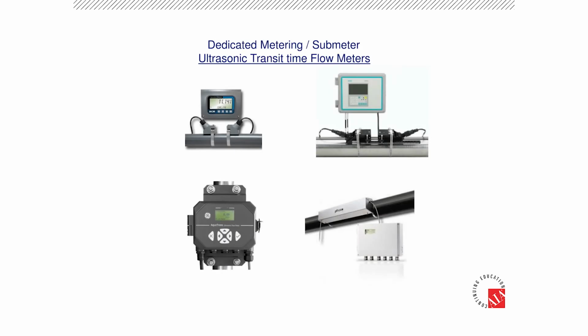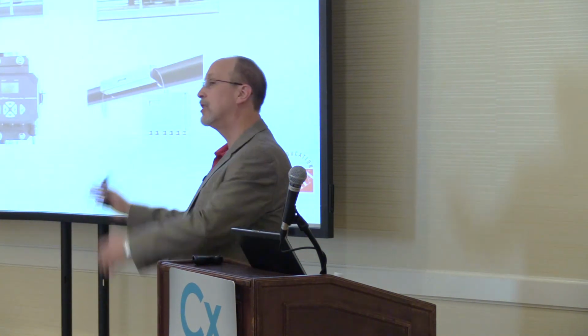Dedicated ultrasonic flow meters are primarily devices that were used in the sub-metering application. Why? Because the prices are getting so low. You can buy a dedicated transit time flow meter for about $2,000 now. The price of a paddle wheel flow meter is about $1,500 to $1,800 without any communications. Put a hole in the pipe, service it once. The ultrasonic flow meter just became less expensive than a paddle wheel flow meter.